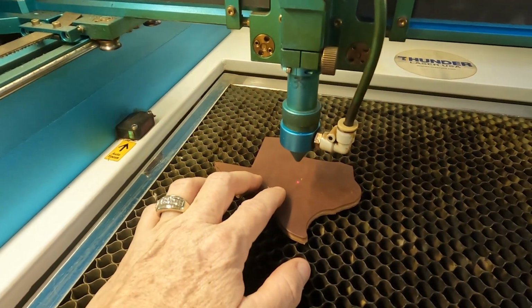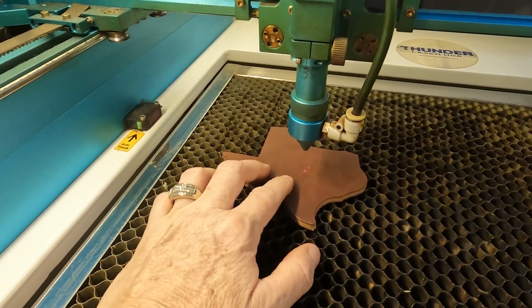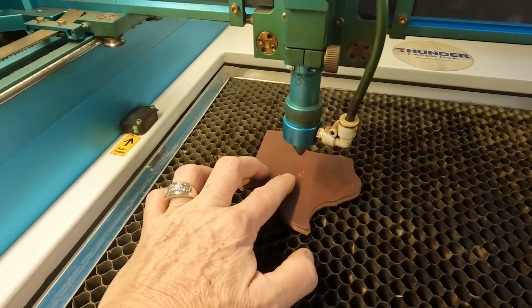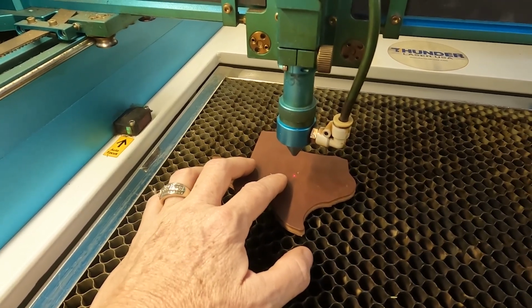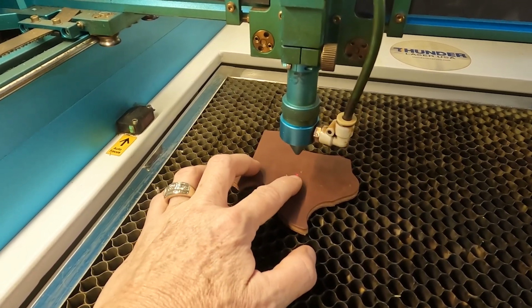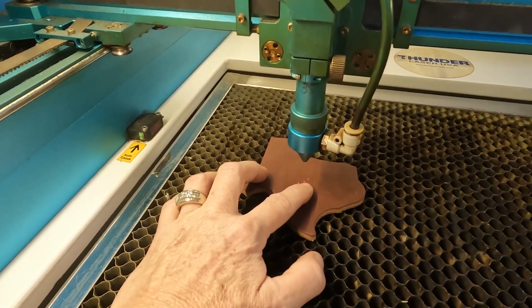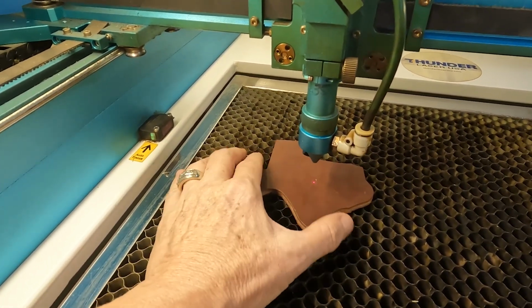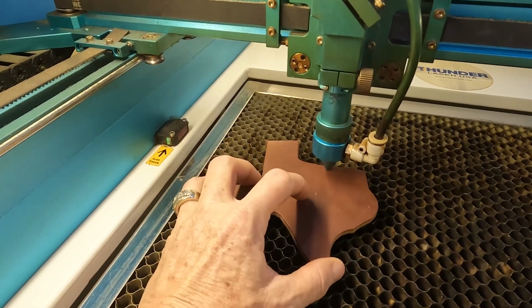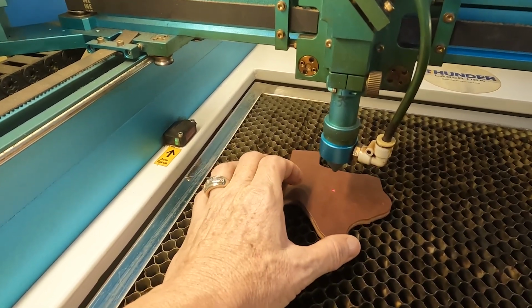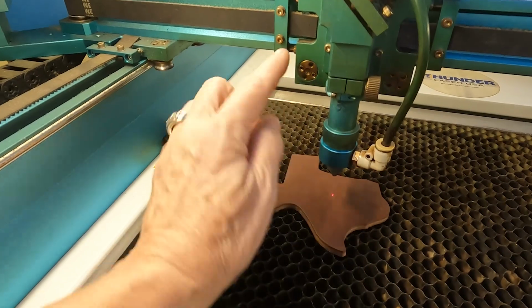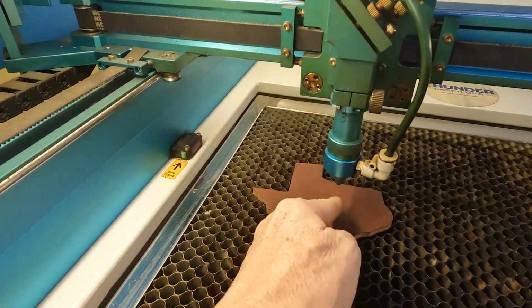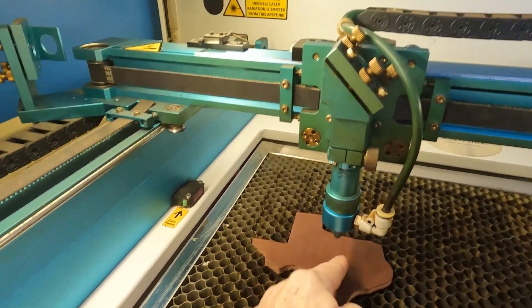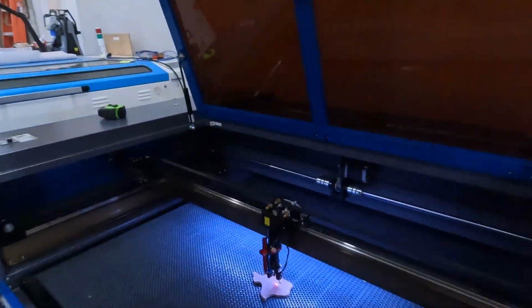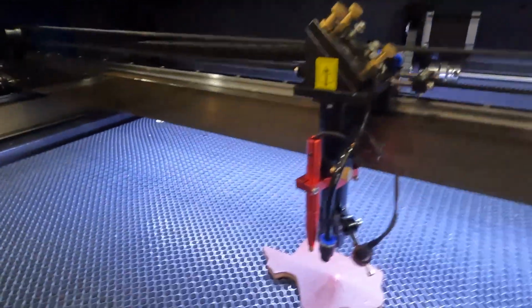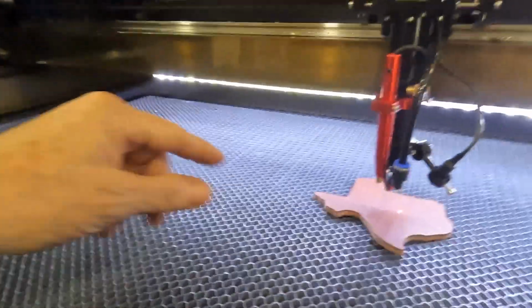I don't rely on it as an absolute, this is the exact spot. It's probably within a couple of millimeters, maybe 1 or 2. But the way this is set up, I know this is probably where, if like this scratch on this piece of Texas, if I put my laser here, that's pretty much where it's going to be. And it is going down through the cone to right there. So that's one difference. On this machine, your red dot does not funnel through the back of the machine.